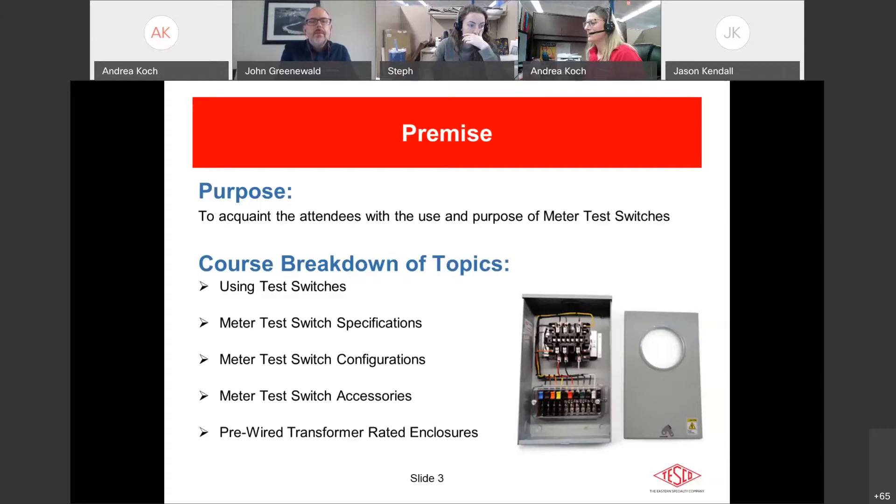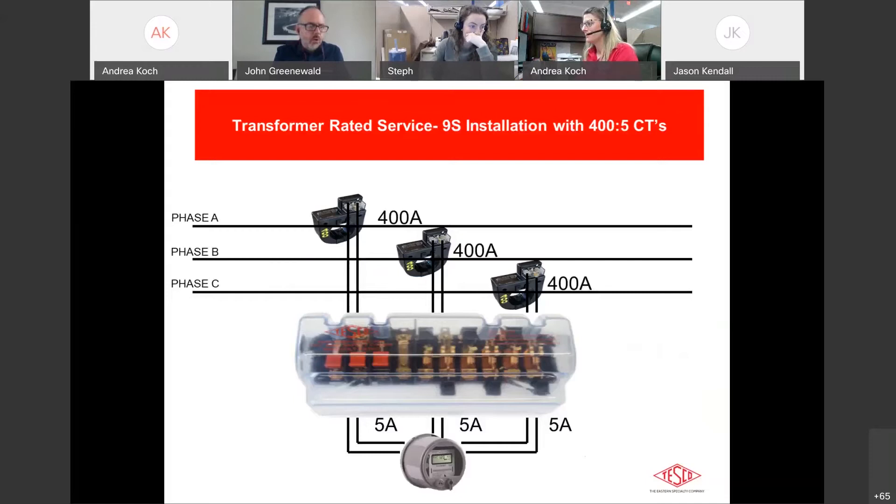The main reason for using a test switch in a transformer rated service is so that you can interact with either the meter or the CT for testing or changeout safely, without disrupting what we call the CT loop. In a typical 9S service with 400:5 CTs, current comes from the service through the secondary side of the CT, through your test switch, over to your meter, back out, and back up through your test switch — that's the CT loop you never want to disrupt.